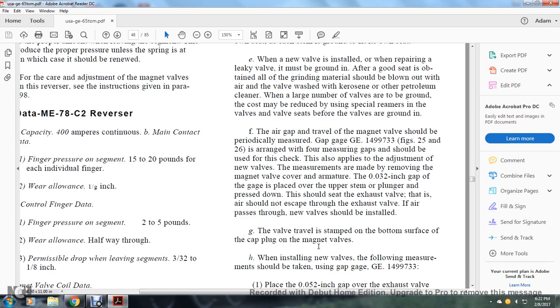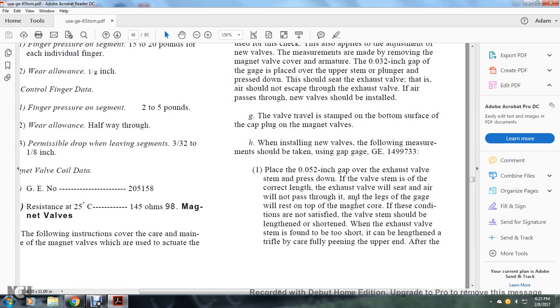After installation, the air gap of the magnet valve should be periodically measured with gap gauge GE 1499-73-3. Figures 25 and 26 show the arrangement for measuring gaps to be used for checking. For a new valve, measurements are made by removing the magnet valve core from the armature. At 32 thousandths of an inch gap, the gauge is placed over the upper stem of the plunger, pressed down on the exhaust valve stem. Air should not escape from the exhaust valve; if air passes through, the new valve should be installed. The valve stem travel is stamped on the bottom surface of the cap plug on the magnet valve. Using gauge GE 1499-73-3, place the 52 thousandths of an inch gap over the exhaust valve stem and press down; if the valve stem is correct length, air will not pass through. If the condition is not satisfied, the valve stem should be lengthened or shortened accordingly.